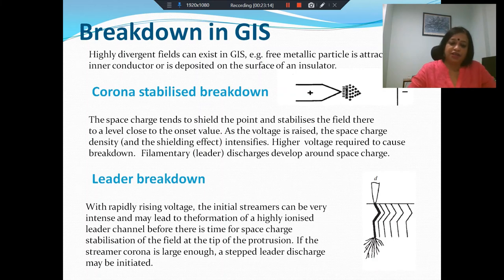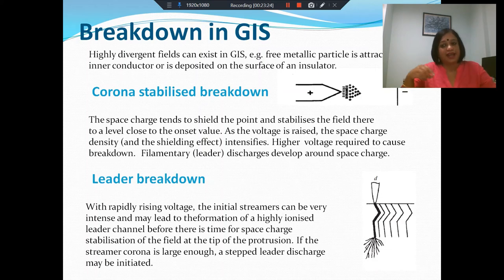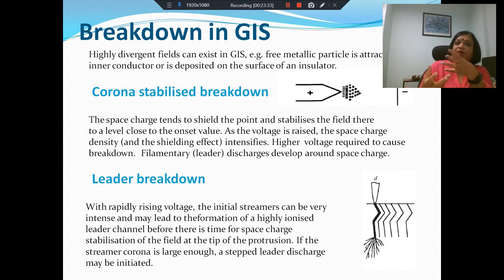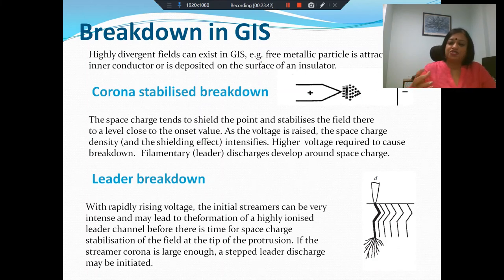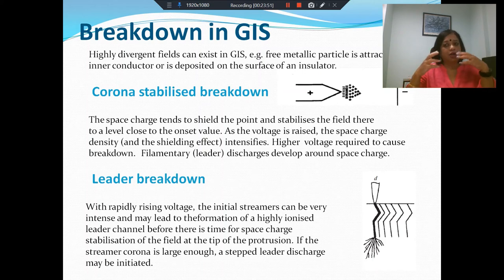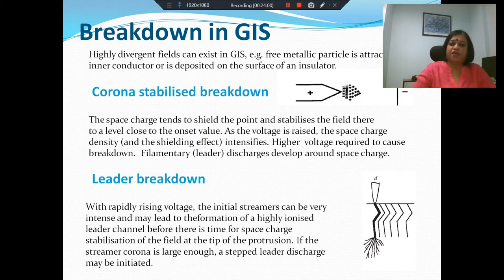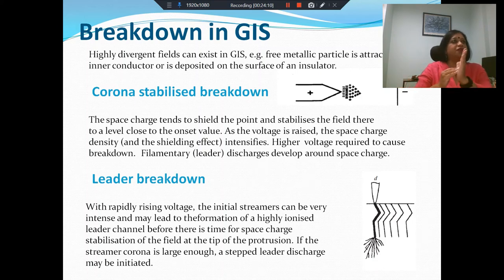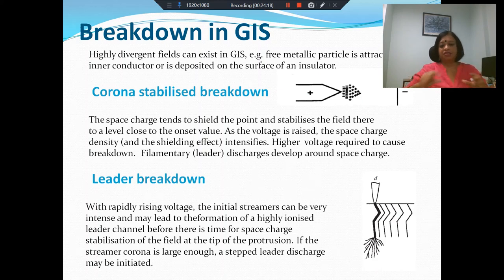The other possibility is leader breakdown. This is mostly seen when you have a rapidly increasing voltage. If the voltage increases rapidly, there will be some initial intense streamers. Instead of having corona that causes stabilizing, you will straight away have intense streamers, and these will lead to the formation of a highly ionized leader channel. The space charge needs some time to accumulate to provide stability. When raising voltage slowly, space charge accumulates and brings down the field, achieving some balance.